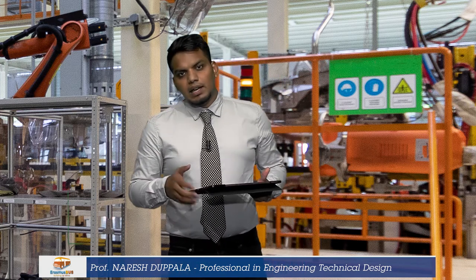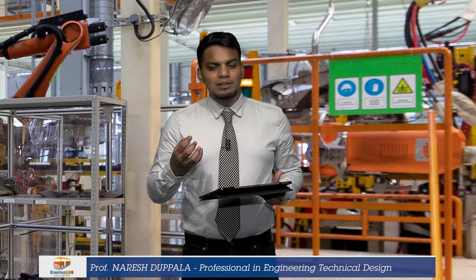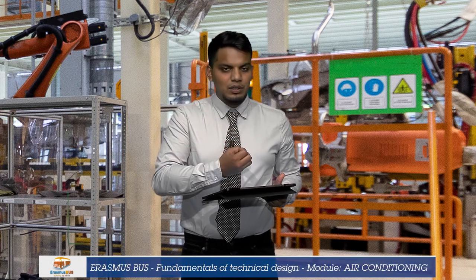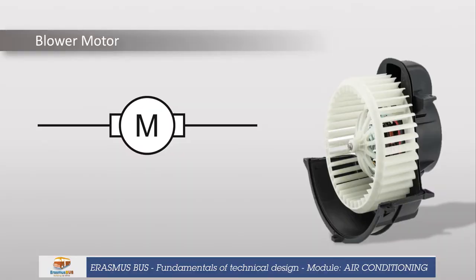A blower motor is a fan which will be located next to each evaporator and condenser. Normally, a motor fan is represented with the letter M inside a circle, with two terminals connected to it for the supply. The two small boxes next to the circle represent brushes. If it's a brushless fan, these will not be present in the symbol; if it's a brushed fan, the two small boxes will appear. The symbol we are currently using is for a brushed motor fan.